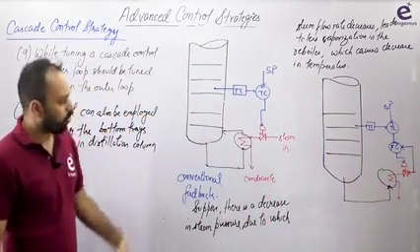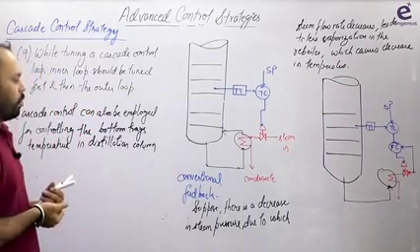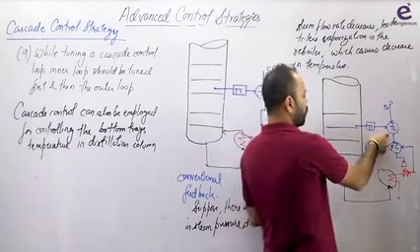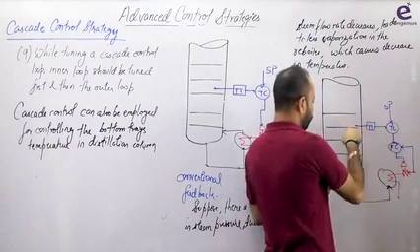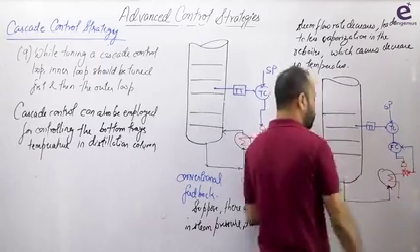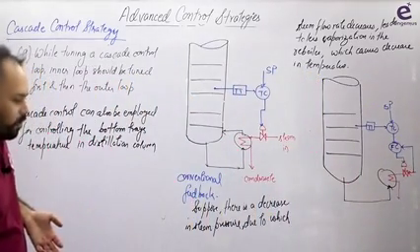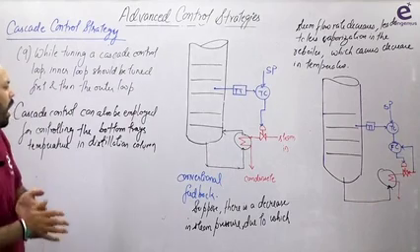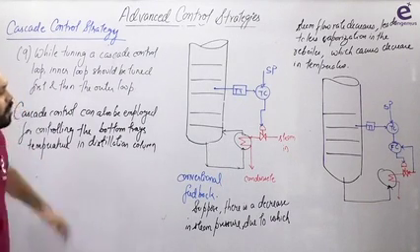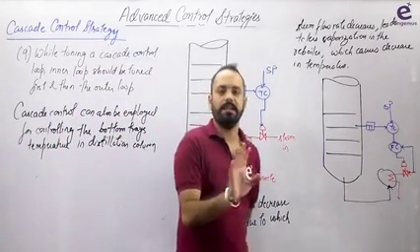In this case also, the instruction to the flow controller is given by the temperature controller. So if you ask me, sir, in this case which one is the primary controller? TC is the primary controller, the temperature is the set point, and the flow controller is the slave controller. This is the manipulated variable, and you can again see there are more than one measurement. I was trying to control the temperature in this case. It's not necessary कि cascade control होना ही चाहिए, ऐसा नहीं है.